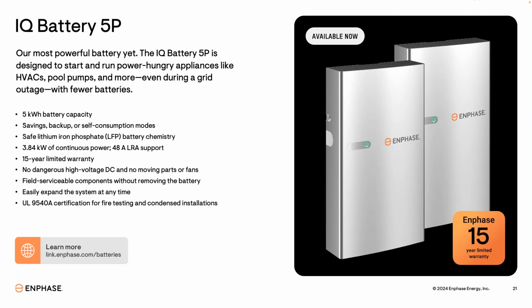The 5 kilowatt hour unit has a continuous power rating of 3.84 kilowatts, which is the same power rating as our previous 10 kilowatt hour battery. So for half the size of the battery, we have the same amount of power, and it even has higher peak power, again for starting big appliances.